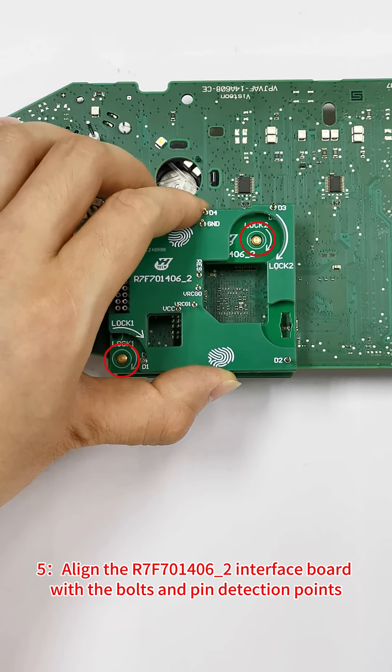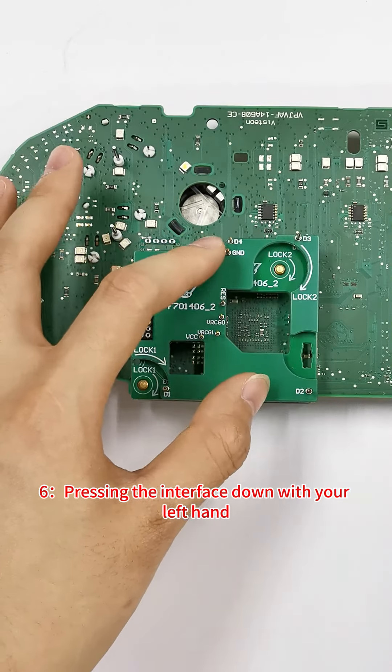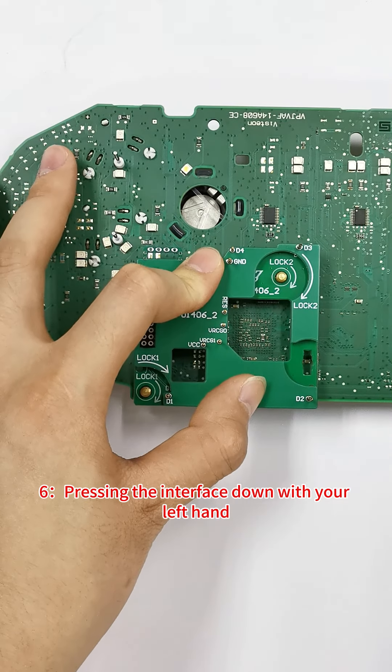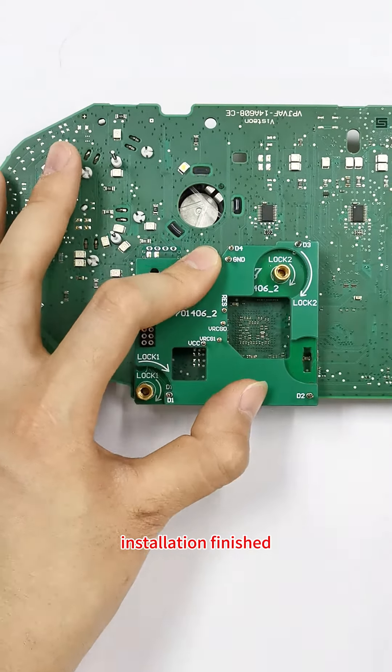Step 5: Align the R7F701406_2 interface board with the bolts and pin detection points. Step 6: Press the interface board down with your left hand and tighten the copper pillar with your right hand. Installation finished.